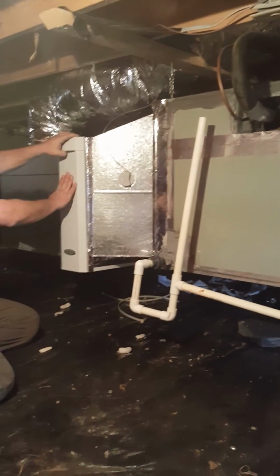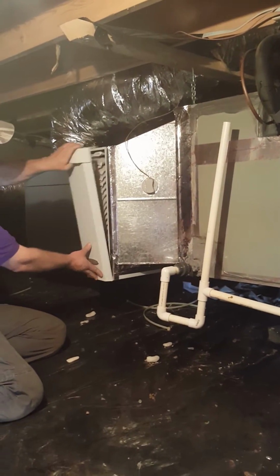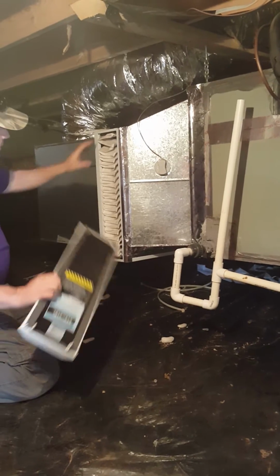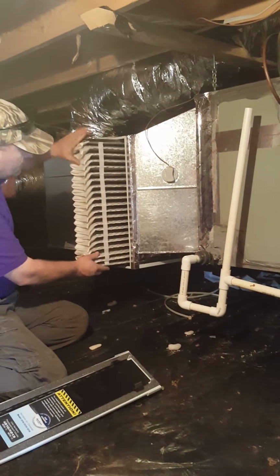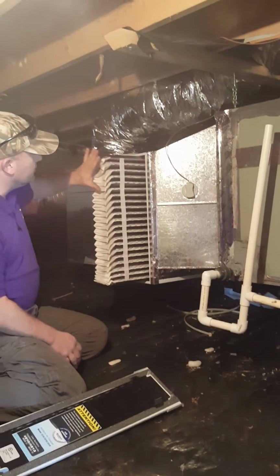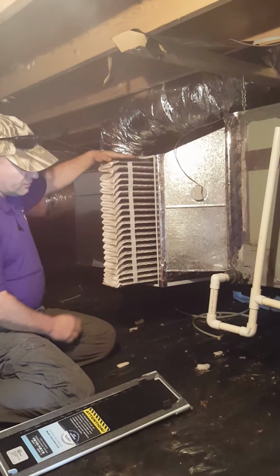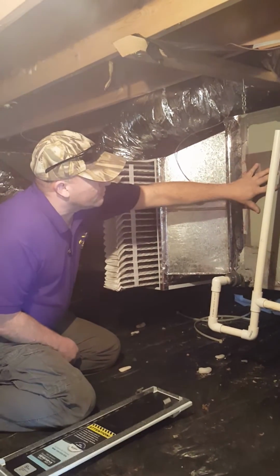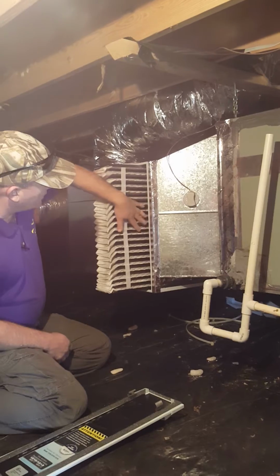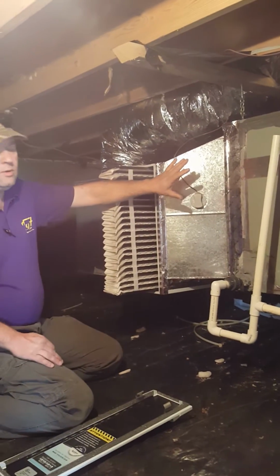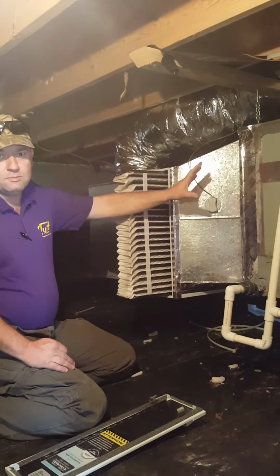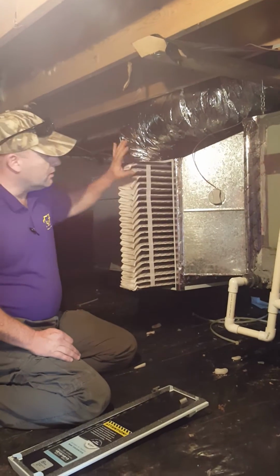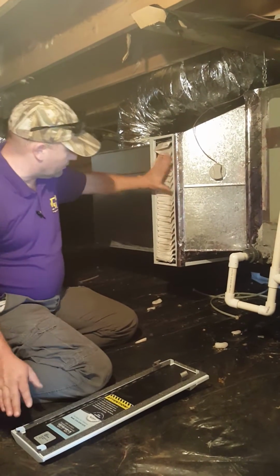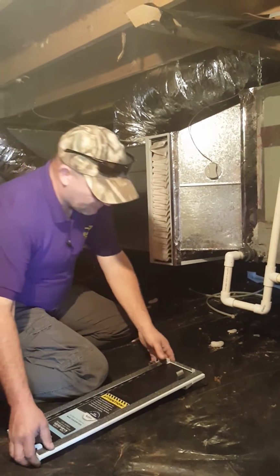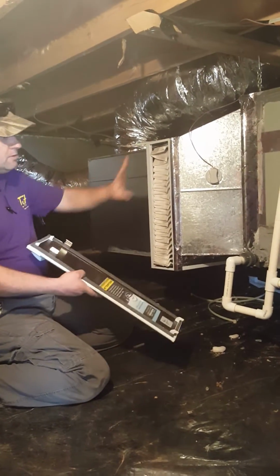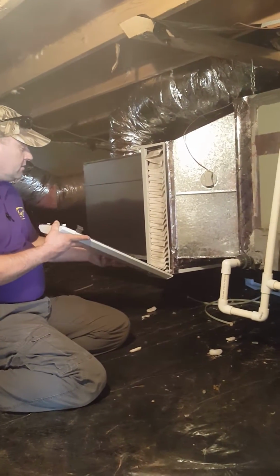The next thing we're going to do is, on this particular unit I have an external Aprilaire filter, so we're going to pull that off. This filter does need changing, but I'll do that another day. While I pull the filter out, the evaporator coil is behind this compartment, so I can see that coil. If it's an accessible coil, we're going to clean that coil up real good and make sure it's clean. But with an Aprilaire filter, you never have to clean that coil. This unit's 12 years old and I've never had to clean that coil.